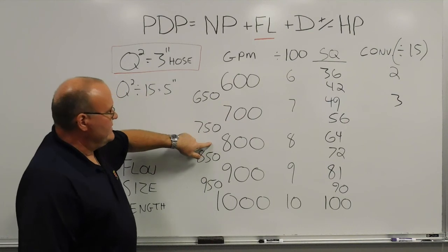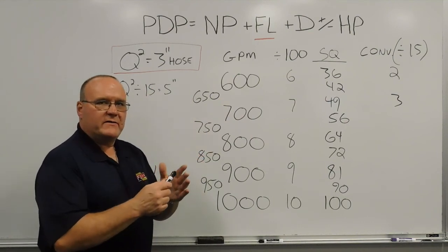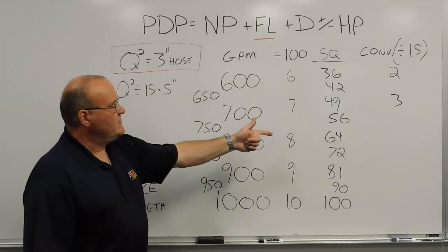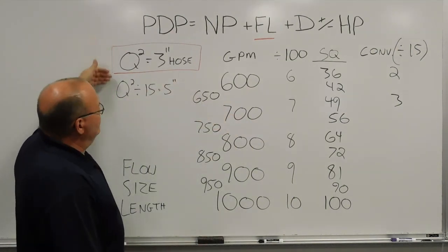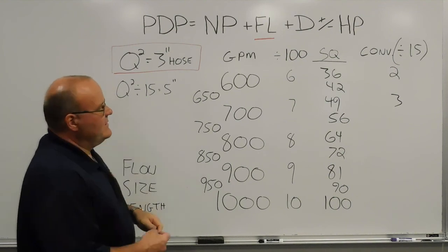For 800 gallons a minute, 600, 700, 800, 8 times 8, there would be 64 pounds of friction loss if it were 3 inch hose, converting that to 5 inch hose divided by 15, you're going to end up with just over 4 pounds of friction loss.